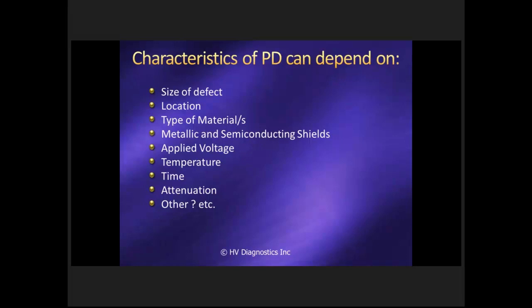Types of materials: there are even materials that are so-called PD resistant. So obviously if you have a cable that's PD resistant, PD may or may not even occur, and if it does occur, it may not be detrimental to the cable. Then the semiconductor shields. Clearly we'll be measuring the PD characteristic, and we have different types of semiconductor shields. They will influence what that PD impulse looks like. The applied voltage: if you bring the voltage up, you may not see any PD at operating voltage. You bring it up higher, you start to see PD.